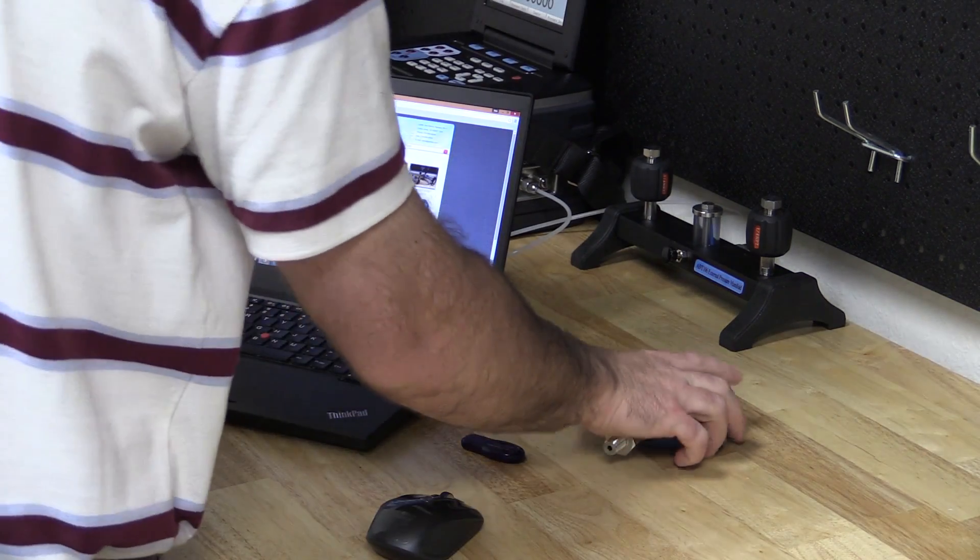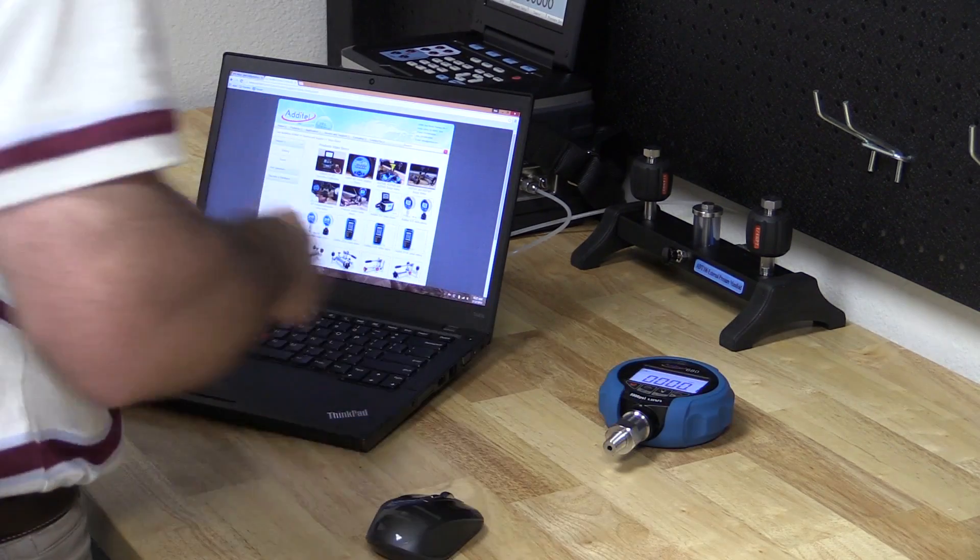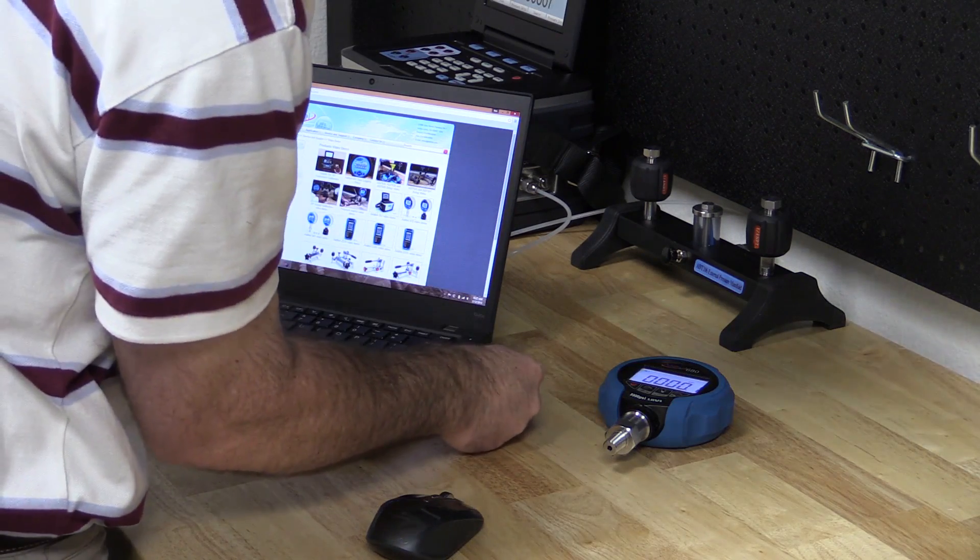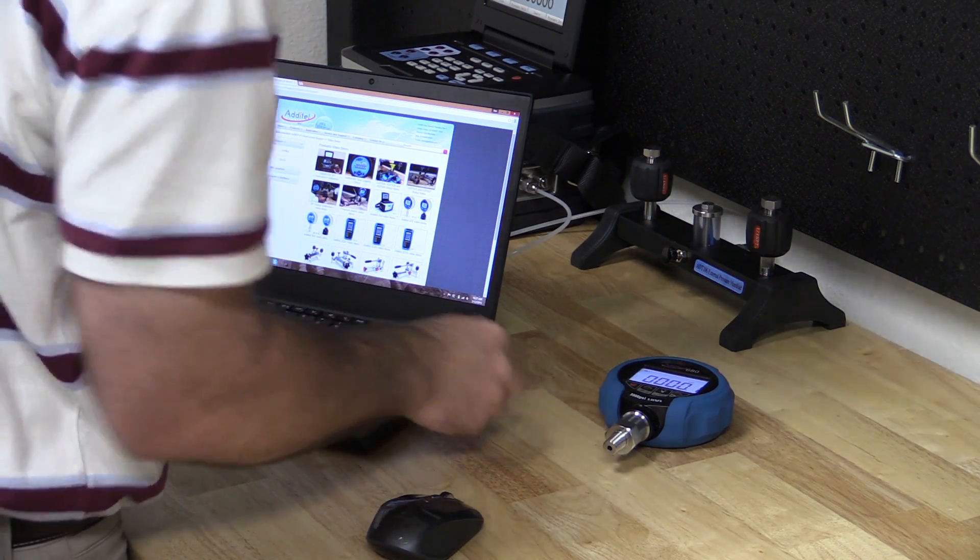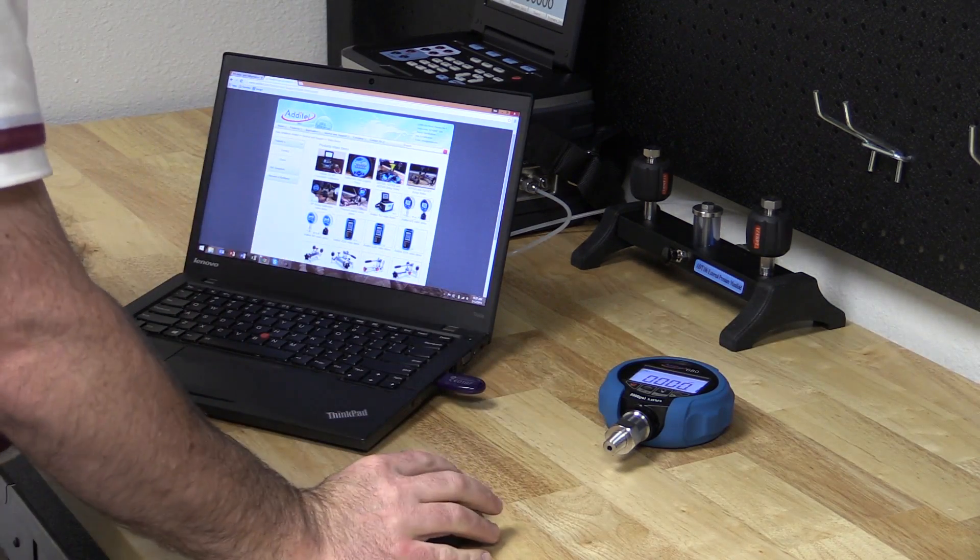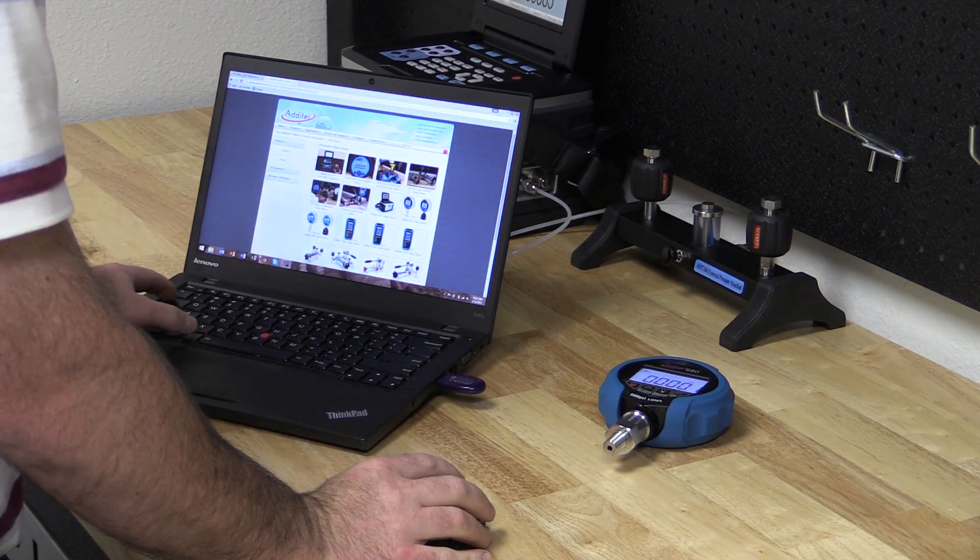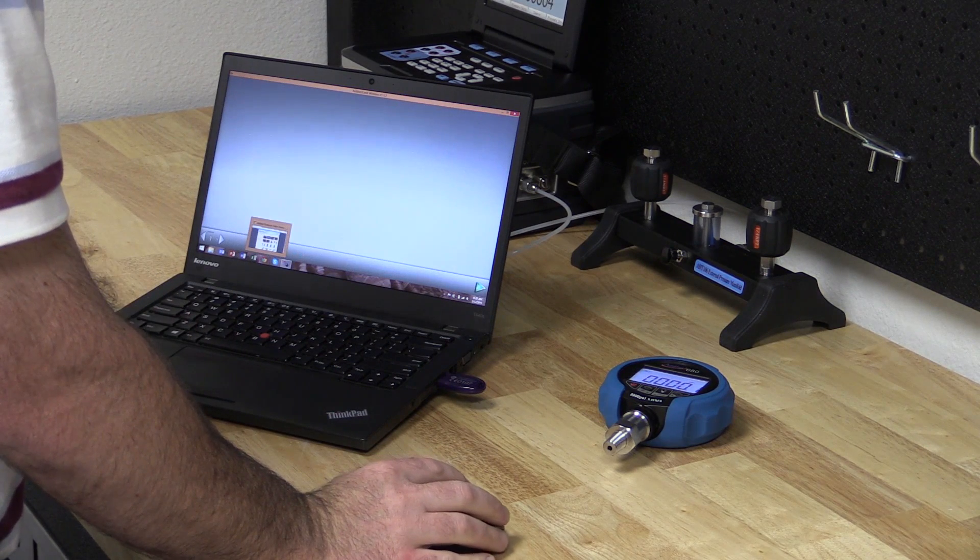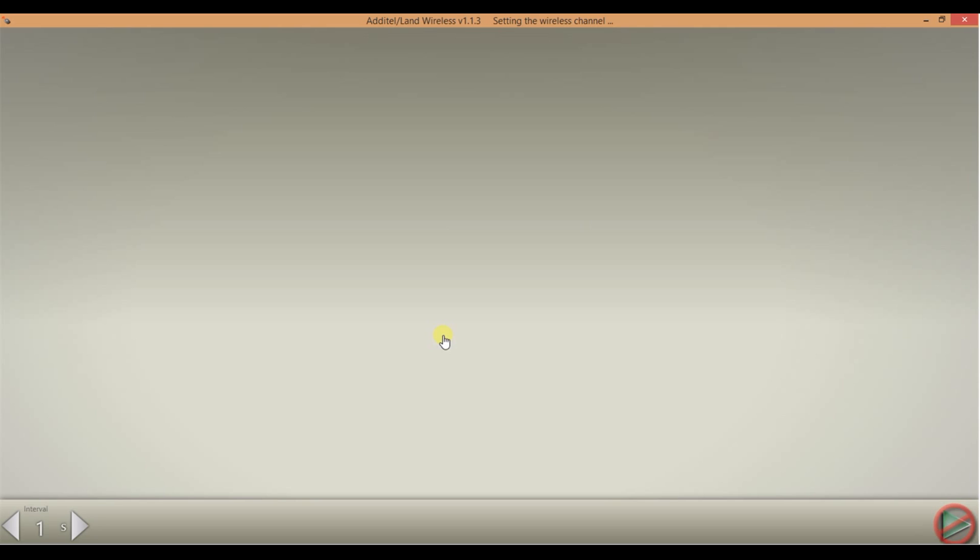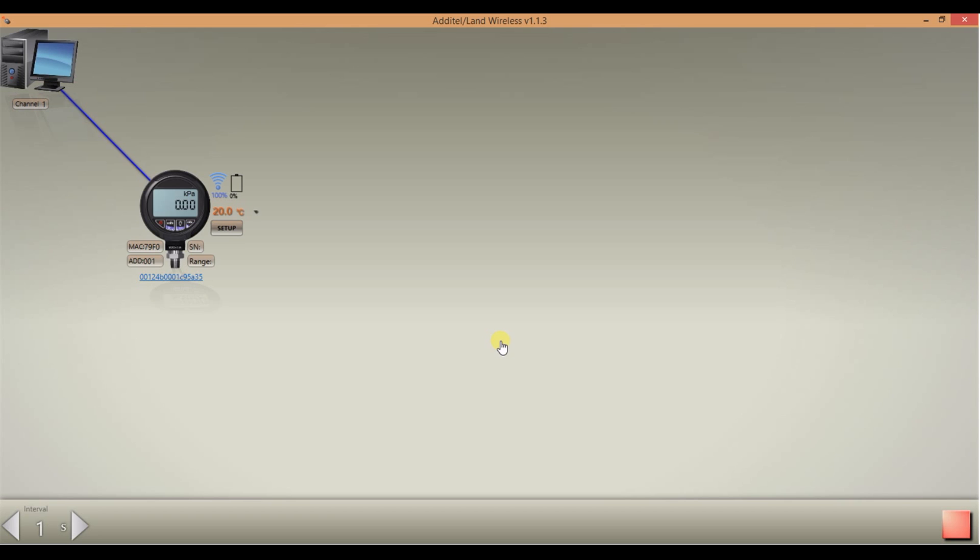First ensure the ADT680W has the wireless activated and the wireless master receiver should be plugged into a USB port on the computer. Open the software application. Click the play icon at the bottom right of the screen. Select the correct channel and wait for the wireless communication to be established. You will notice this by a computer and a gauge appearing on the screen and the wireless icon on the gauge will cease blinking.